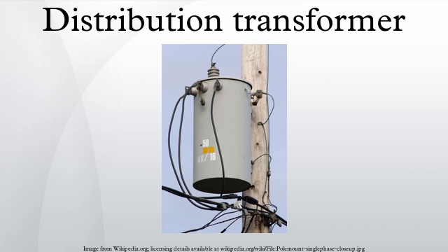Distribution transformers may include an off-load tap changer to allow slight adjustment of the ratio between primary and secondary voltage, to bring the customer voltage within the desired range on long or heavily loaded lines. Pad-mounted transformers have secure, locked and bolted, grounded metal enclosures to discourage unauthorized access to live internal parts. The enclosure may also include fuses, isolating switches, load break bushings, and other accessories. Pad-mounted transformers for distribution systems typically range from around 100 to 2000 kVA, although some larger units are also used.